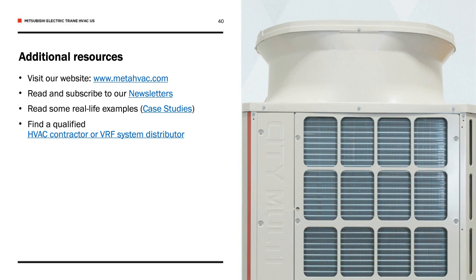Yeah, that's absolutely correct. You heard during my presentation I mentioned BACnet. BACnet has become the standard, especially in the eyes of ASHRAE, the standard protocol on which our industry communicates. It's a 2-wire communication over an MSTP wire, and it can also be IP communication over a standard Ethernet cable. Once you're in that protocol, you can essentially move between technologies and platforms pretty easily. Almost all building automation systems and building management systems have the capability within that type of network.